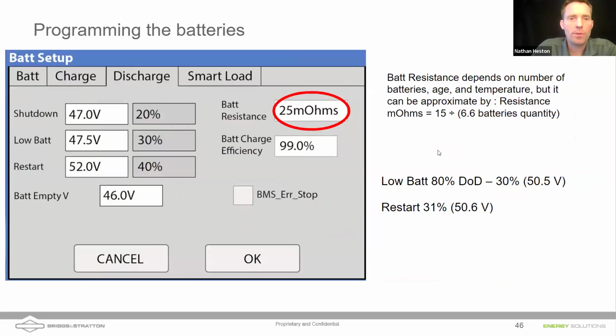One last thing that does need to get programmed in when you're setting up the battery settings is the battery bank's overall resistance. What this allows you to do is, when the system is discharging and you're under load, it does allow you to go below the low battery cutout voltage. So let's say, for instance, your low battery cutout voltage was 47. If you have a certain amount of battery resistance in there and you're drawing a heavy load, some of the overall voltage of the battery bank is lost internally. So we call that internal resistance. And so you might see the inverter run to voltages below what you've programmed into your low battery cutout. And that's simply because the resting voltage is actually above the loaded voltage of the battery bank.